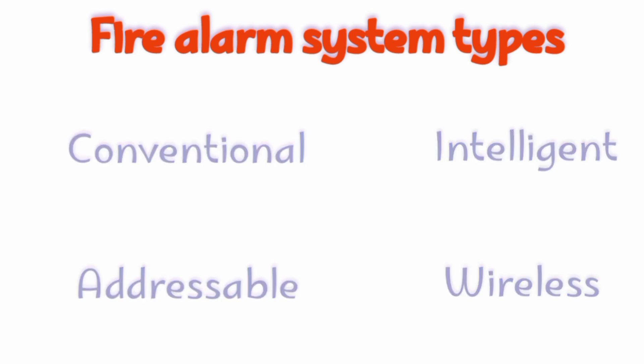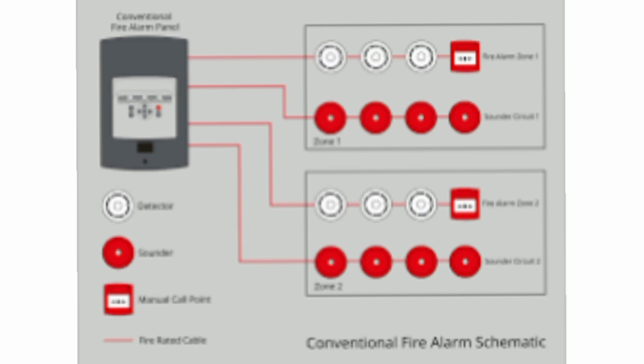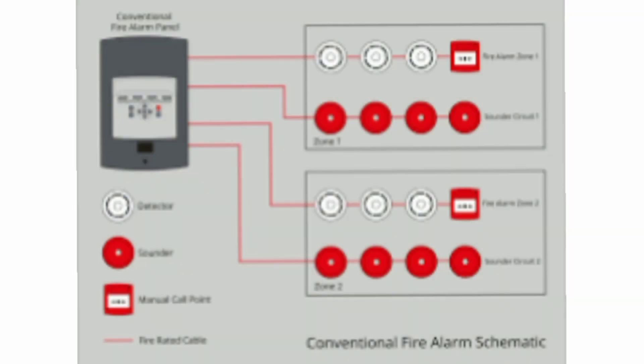In a conventional fire alarm system, multiple fire detectors, manual call points, and heat detectors are in a single zone. If it detects fire or smoke, it will indicate only the zone or area, not the exact single point.